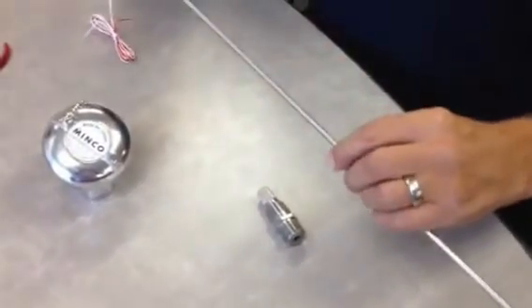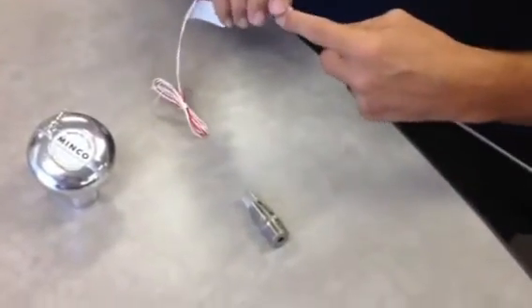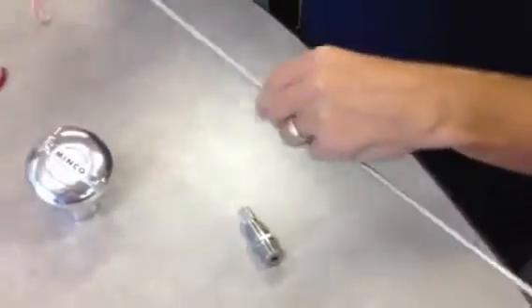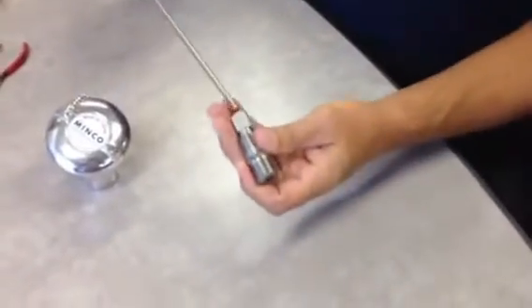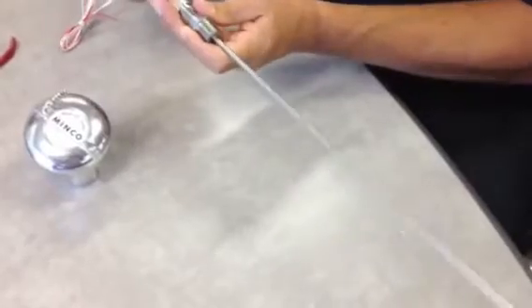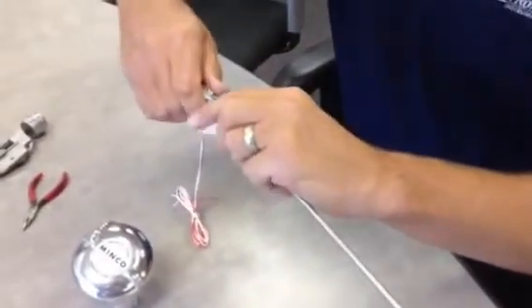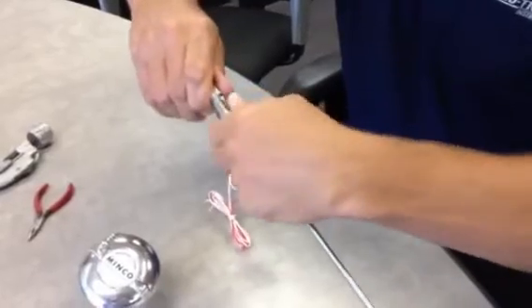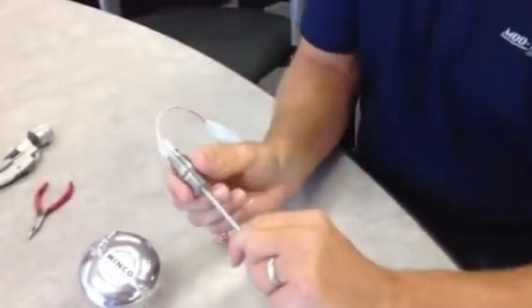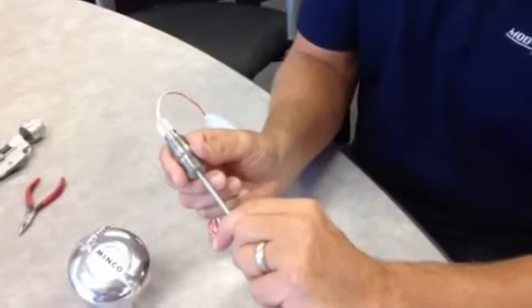So let's assume we've already cut this probe and we're ready to reinstall it back into the bearing. We slide the probe in and it bottoms out onto the bottom of the bearing. You then pull out and turn to the left the knurled knob, which releases the spring inside. And you'll have spring tension onto the bearing surface.